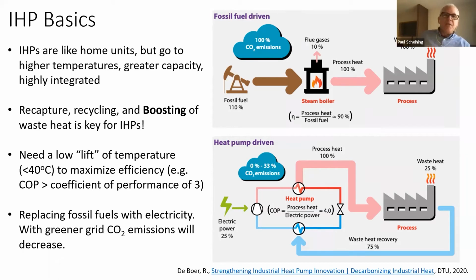To maximize efficiency, what you're trying to do is get the coefficient of performance, the COP, generally to be greater than 3. That's because you're using electricity to drive that heat pump, and you want to deal with the thermodynamics of a COP of greater than 3. In this case, in the diagram, we're showing a COP of 4.